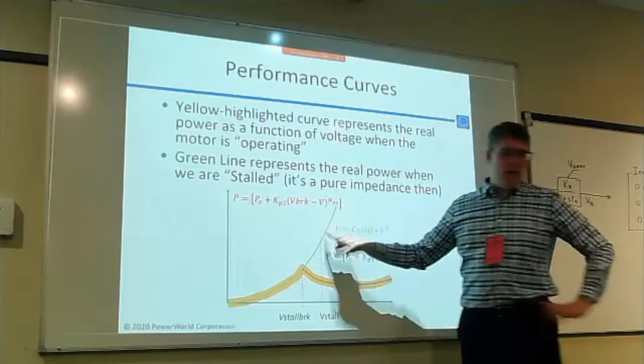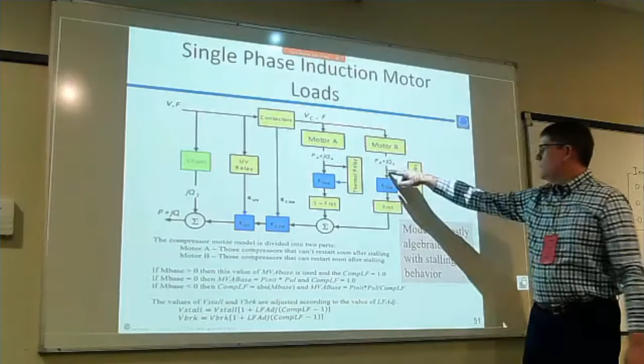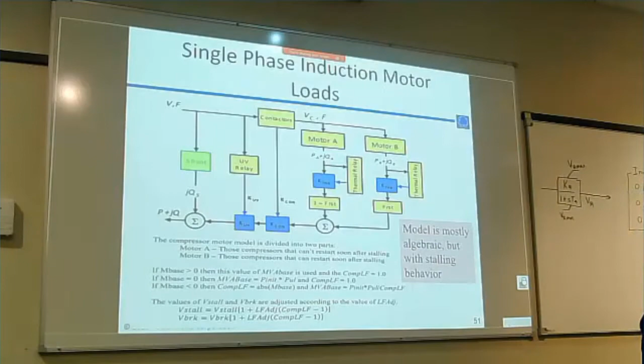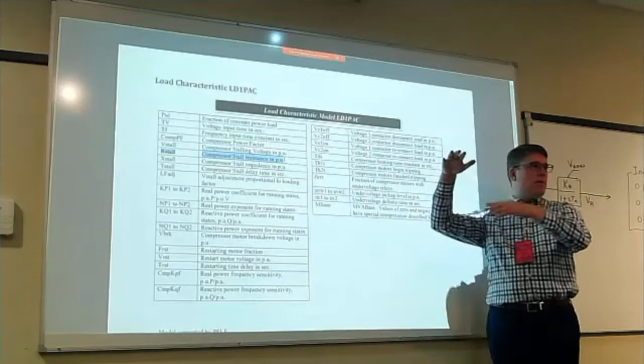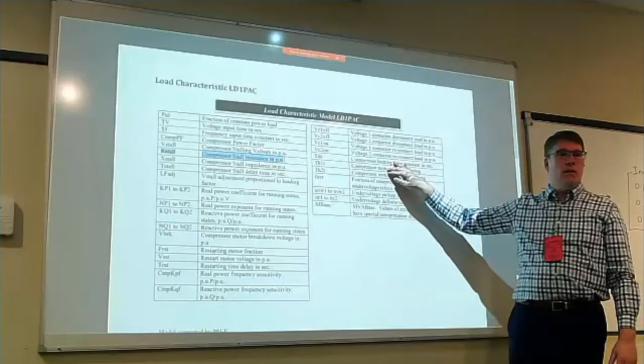And the way we trip them, actually, I guess we don't really show it that much in here. You're just integrating the current. So right here, we're going to calculate the current squared times the stalling resistance. So we're going to say I squared R, those are losses that are heating up the motor. And we're going to integrate those losses over time. And there's a time constant in here that is the heating time constant. And this is telling you when they start tripping and when they finish tripping, so that eventually they trip out.